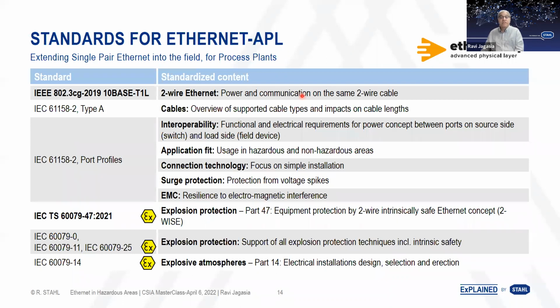Definitely the IEEE 802 standard with the 10 base T1L forms the basis of the two-wire. The cables from IEC 61158 became the standard requirements for Type A cables, and then also the port profiles. We'll come to the port profiles a little later, but there was the requirement that we wanted interoperability. We wanted an application fit for hazardous and non-hazardous areas. We definitely wanted connection technologies to be consistent to simplify installation, definitely take care of surge protection, and EMI and EMC, the electromagnetic interference. We definitely need to adhere to this two-wire solution, which evolved for intrinsic safety. So that was the standard adopted.